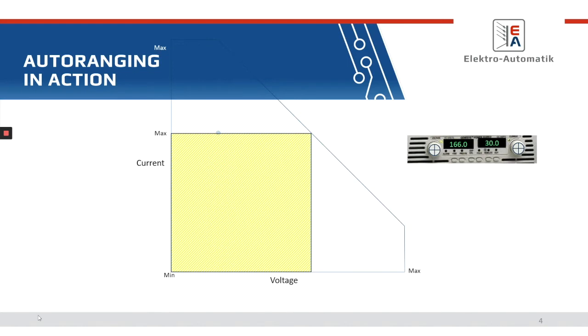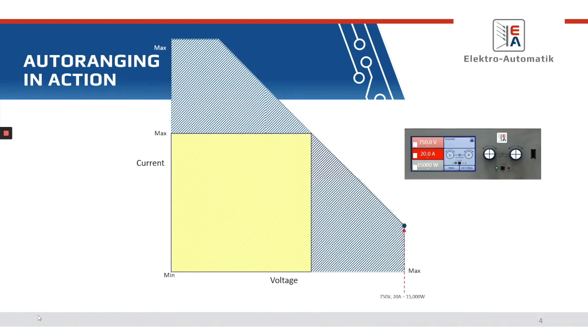So now let's take a look at an auto-ranging power supply. One of the things you'll notice is that we went with a higher voltage model. Yes, you could get a 500 volt auto-ranging power supply, but why would you? Why not go to 750 volts, again, plan for the future, when you know you can still hit your voltage and current combinations and those cardinal points that you need from a power perspective. So again, 750 volts, 20 amps, you got your 15 kilowatts. Program down in voltage, say down to that 500 volt mark, and you're still at that same 500 volt, 30 amp, 15 kilowatts that you were with that other power supply.